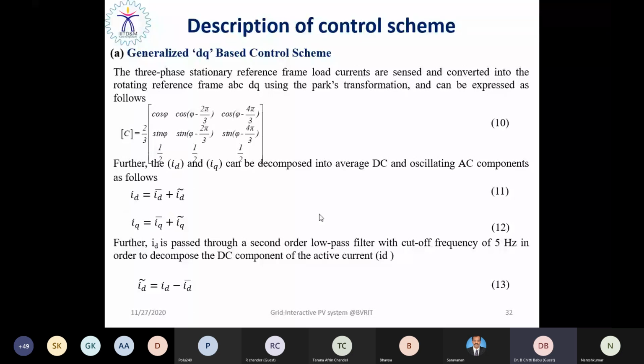As we are implementing a control strategy on this grid interactive power converter, that control has to handle both the DC as well as AC variables. So input side DC variable and output side AC variable. So it has to have proper coordination while converting ABC to DQ. So we use the Park transformation for transforming the AC quantities into orthogonal quantities, so that the output is in terms of ID and IQ components. Basically, they are called the orthogonal components or DQ components. So the ID component represents the active power current component, and IQ represents the reactive power current component. So it is composed of average DC and oscillating AC, right? As they are orthogonal with each other, this oscillating AC component has to be nullified during the transformation.